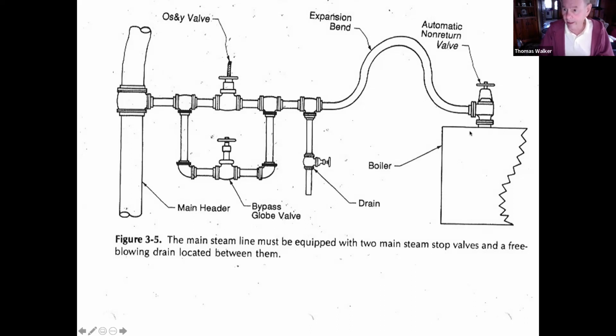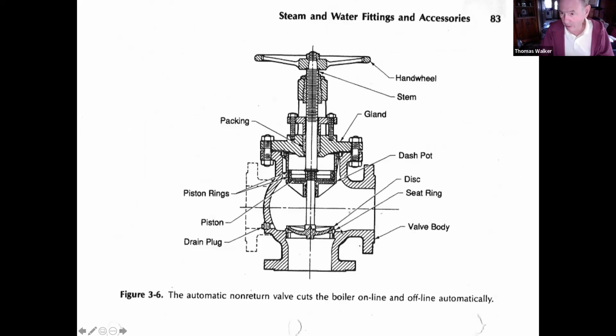The non-return valve is optional. So they don't have many questions about this. But this is a nice feature, all right? The non-return valve, while it can act as an isolation valve if the stem is screwed down, when it's backed off, it will automatically isolate the boiler if the boiler pressure goes below the header pressure. That's a nice feature. The question on the state exam asks the direction of steam flow through the non-return valve. It is out of the boiler only. That's the only way steam can flow when this valve is in play.